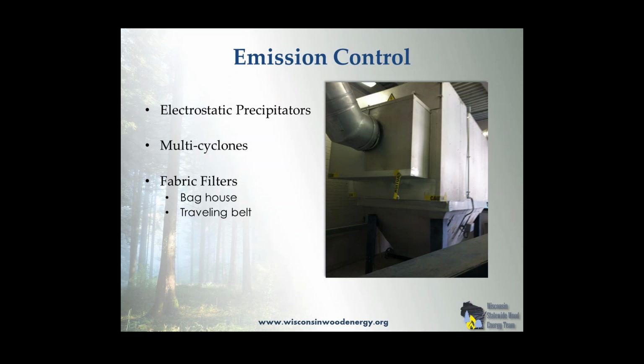Again, this is an electrostatic precipitator. It was installed in a boiler room in Maine. I want to point out a problem with these. You can kind of see the light coming through behind this precipitator, and they brought in combustion air to the boiler and blew it across the electrostatic precipitator and got lots of condensation in it, which is a big no-no. So that was not a good plan, but basically they can be fairly compact and fairly simple. They are a lot lower labor, and they're very reliable and very effective at emission controls, especially for finer particles.